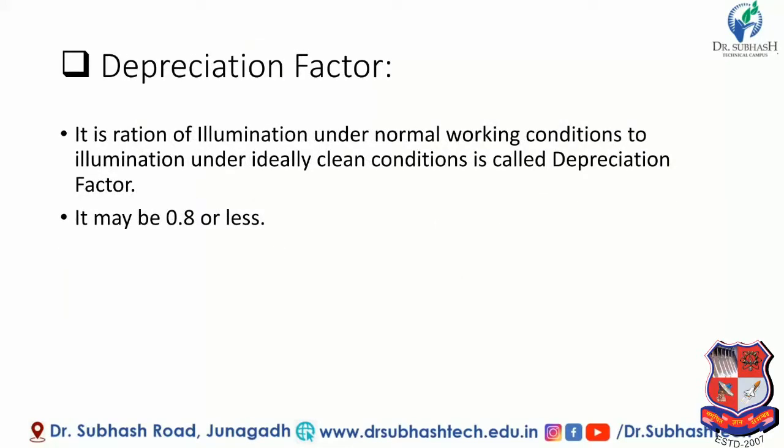So next, depreciation factor. It is a ratio of illumination under the normal working condition to the illumination under the ideally clean condition, and is called depreciation factor. Its value may be 0.8 or less than 0.8.